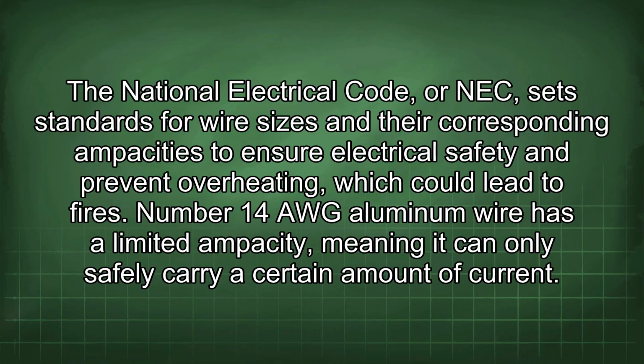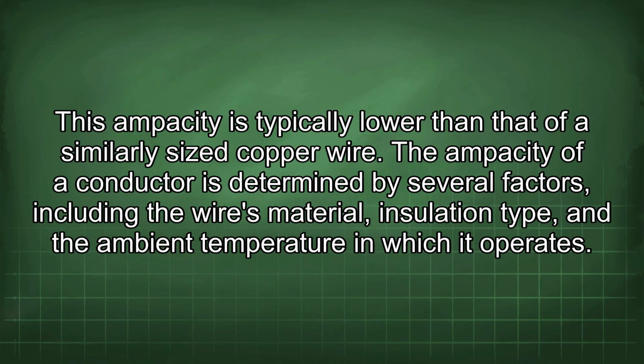The National Electrical Code, or NEC, sets standards for wire sizes and their corresponding ampacities to ensure electrical safety and prevent overheating, which could lead to fires. Number 14 AWG aluminum wire has a limited ampacity, meaning it can only safely carry a certain amount of current. This ampacity is typically lower than that of a similarly sized copper wire.